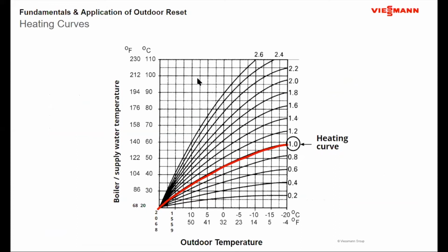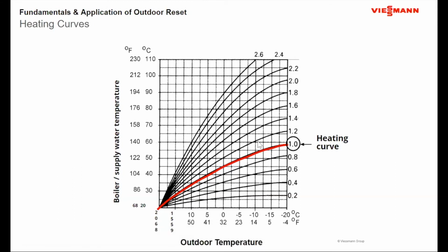Okay, so when we do outdoor reset, one of the things that has to be determined is what's referred to as a heating curve. You may hear it referred to as a reset ratio, or you also might hear it referred to as the slope. So what we're really talking about is the shape of this. These curves actually have a curve to them. Sometimes you'll see them more as a straight line, but this heating curve sets the relationship between outdoor temperature and the boiler water temperature.